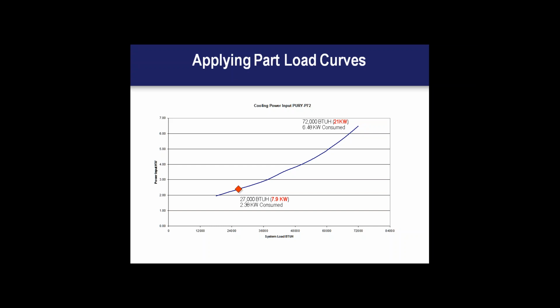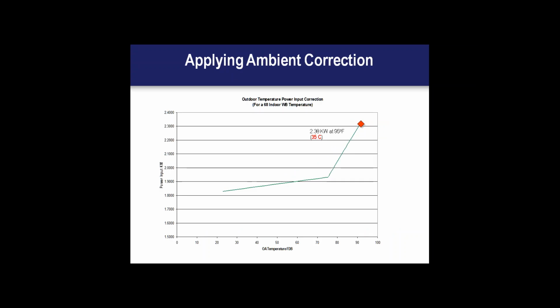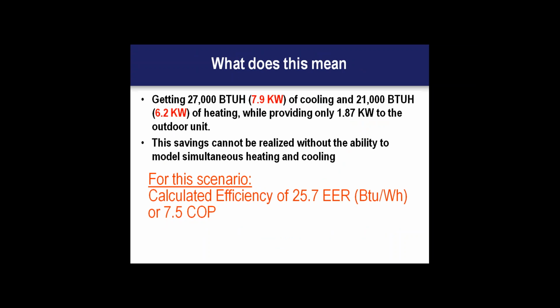Now again, this is at a 95-degree day, and we have to apply those ambient corrections. So where normally we would consume 2.38 kW at that 95-degree day or 35-degree Celsius day, at this condition, since at this hour was 50 degrees, that equates to roughly 1.87 kW. So what does this mean? We've just gotten 7.9 kW of cooling, 6.2 kW of heating.